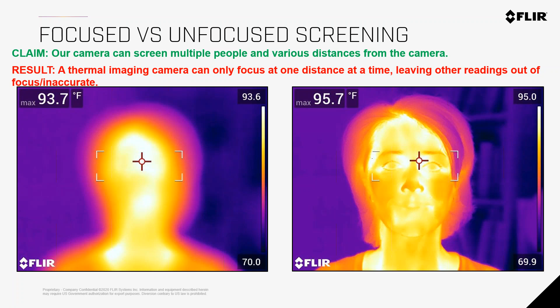So if you are doing these screens with multiple people coming, or trying to take temperatures of everybody in a line, with one person at point A, point B 3 feet behind that, and point C 5 feet behind that, and so on, only one of those people is actually going to be in focus at a time. The camera may pick up some facial recognition or give you a temperature reading, just like our camera gives you a reading on an unfocused object, but it's not going to be accurate, because the pixels aren't getting all the data and sensitivity they need to give you a good image and good results. So the result of trying to screen multiple people, when one or several of them are going to be unfocused, is that the thermal imaging camera can only focus at one distance at a time, leaving other readings out of focus and inaccurate.